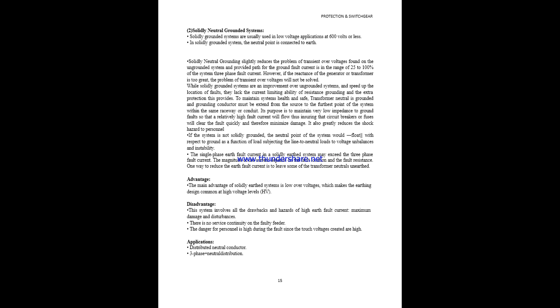So one way to reduce the earth fault current is to leave some of the transformer neutrals unearthed. The main advantage is low overvoltages, which makes this earthing design common at high voltages. The disadvantage is that it may involve drawbacks causing maximum damage and disturbances. There is no service continuity, and there is danger for personnel. It is applied for distributed neutral conductor and three-phase neutral distribution.